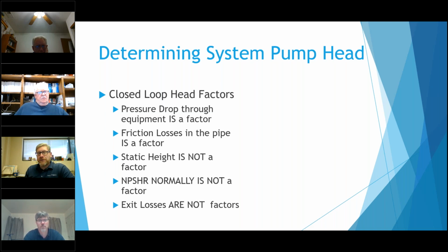I've got a picture later that shows what an impeller looks like when it's had cavitation, but essentially it looks like someone hit it with a ball peen hammer, and it's got these little dots all over it. It can eventually whittle the impeller away to almost nothing. But in a closed system, since the PRV sets the system pressure, and then the expansion tank or compression tank maintains that system pressure, there's usually enough pressure at the pump suction that you don't have to worry about the net positive suction head. Since the water never leaves the system, the exit losses aren't an issue with pumping a closed loop system.